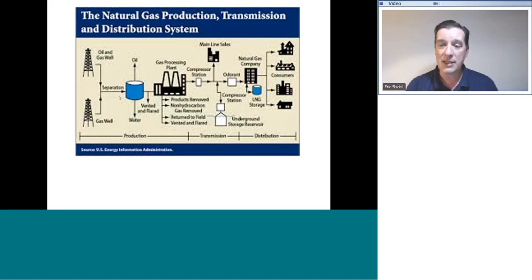We do have a question in the box. The question is, does the additive change the BTU rating? The natural gas providers that put in the additive, they may also put in other agents with the natural gas to deliver it to the end user. And some of those additives can change the BTU content, which is why I mentioned earlier the difference between summer gas and winter gas.